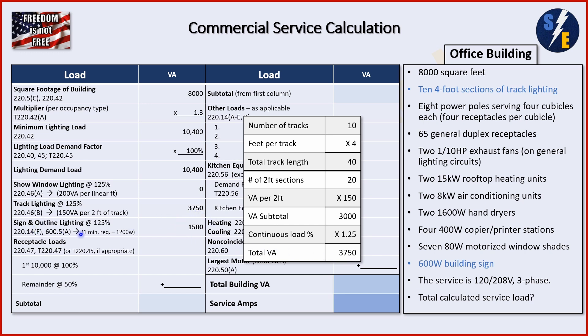Next is sign and outline lighting. We have a 600 watt building sign. Under 220.14F we must comply with article 600.5A, which requires a minimum of one 1,200 watt circuit for any sign on a building accessible to the public. Even though our sign is only 600 watts, we must figure a 1,200 watt minimum. Since it will be on more than three hours at a time it's a continuous load, so we multiply by 125%. 1,200 times 125% equals 1,500 VA for sign and outline lighting.